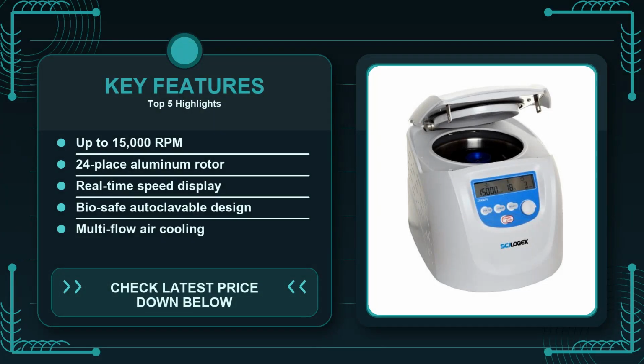On the flip side, there are clear scenarios where this machine isn't the best match. If you need to spin larger volume tubes, say 15 milliliter conical tubes, or you regularly require ultracentrifugation speeds above 20,000 revolutions per minute, you'll quickly outgrow the SCI 24's capabilities. The 24-slot rotor is perfect for high-throughput microtube work but becomes a limitation when you have to accommodate a mix of tube sizes or need a single large tube. Also, if you're operating on an extremely tight budget under $1,000, the initial price tag may still feel steep compared to the cheapest knockoffs, even though those cheaper options often cut corners on cooling and safety features.